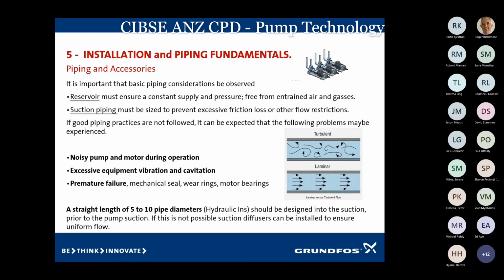If you cannot do that, then we put suction diffusers, and we can mount those onto the inlet of the pump. A suction diffuser is basically a 90-degree bend, and it takes out the turbulent water and causes it to be nice and laminar going into the pump, and it works quite happily in that way.